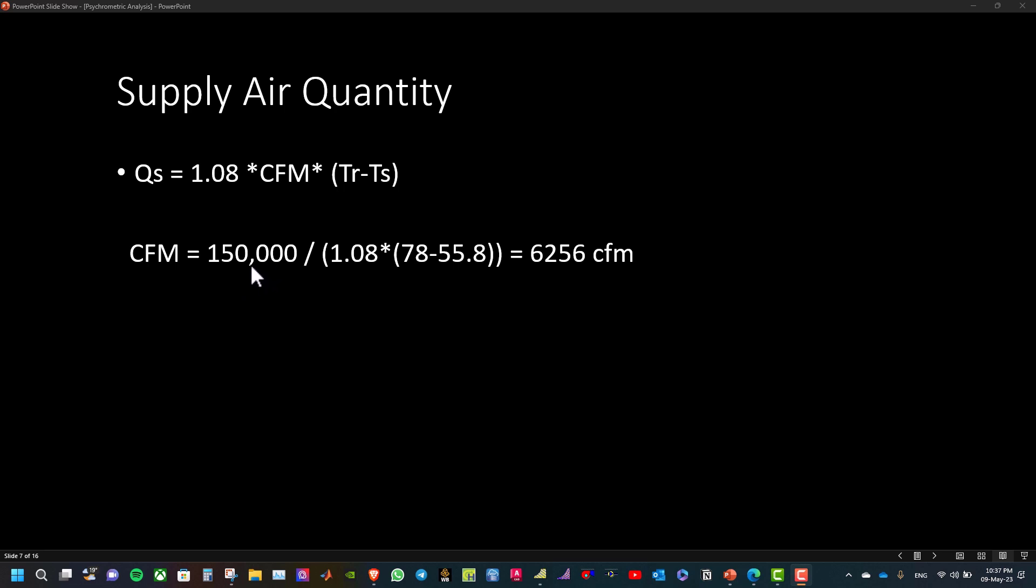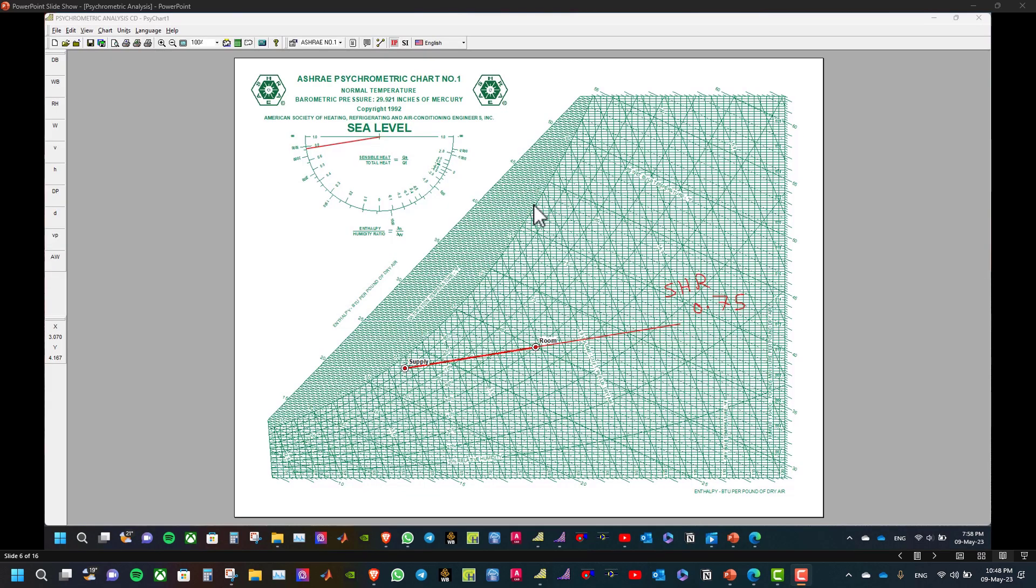which is the sensible heat gain, over 1.08 multiplied by 78 minus 55.8, which is the TR minus the TS, equal to 6,256 CFM. And this is the summary of the scenario.